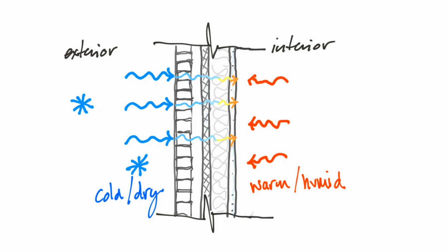the cold, dry air outside doesn't allow the cold to radiate its way through your wall and hit the interior of that drywall. It gets stopped somewhere in the middle by your insulation, and the dew point is within your wall system and doesn't make it to the interior. So the interior surface of your wall is warm, above the dew point, and when your warm, humid air hits it, no problems.